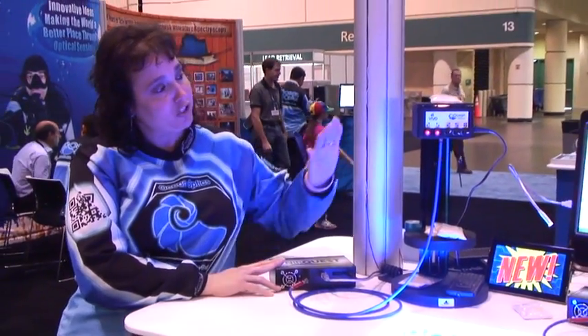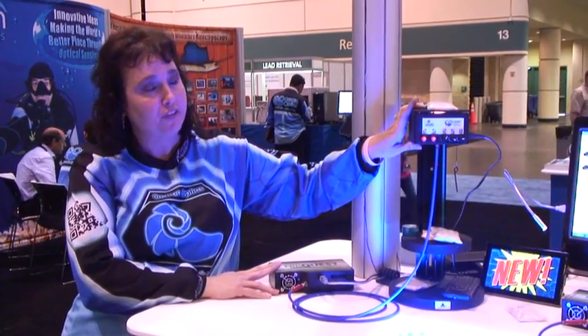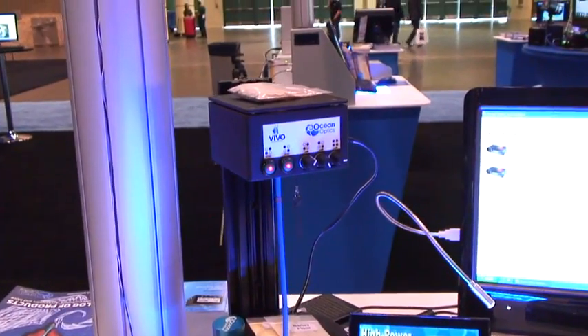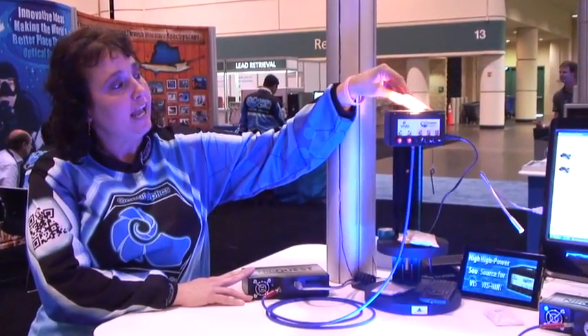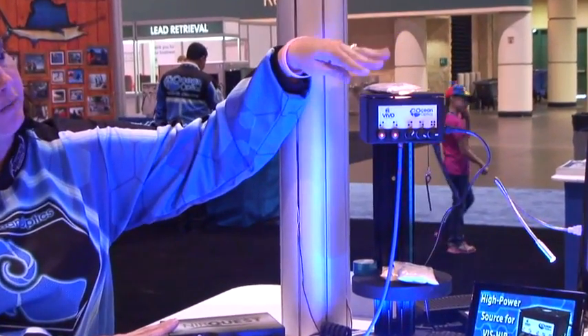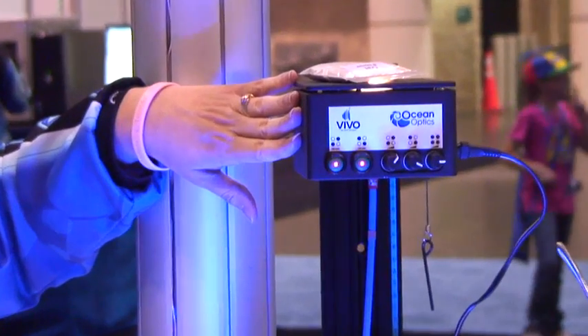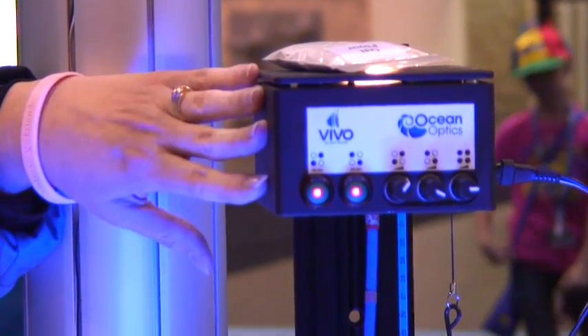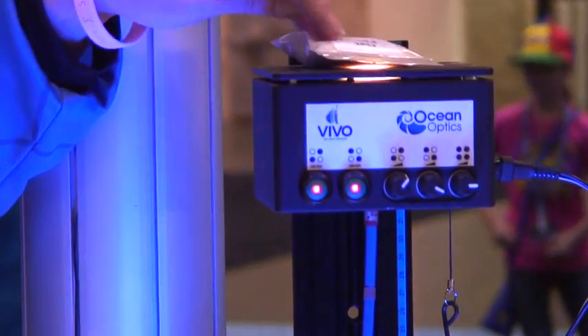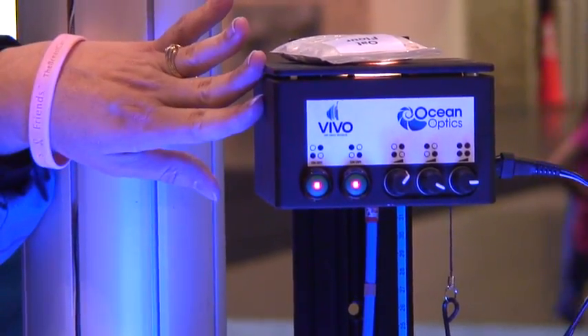The NIRQuest is making a measurement in conjunction with our Vivo light source, which is a diffuse reflection light source, and we're making some measurements of grain samples. The Vivo has four tungsten halogen light sources, which can be controlled individually to give incredible illumination to a surface so that you can make diffuse reflection measurements.